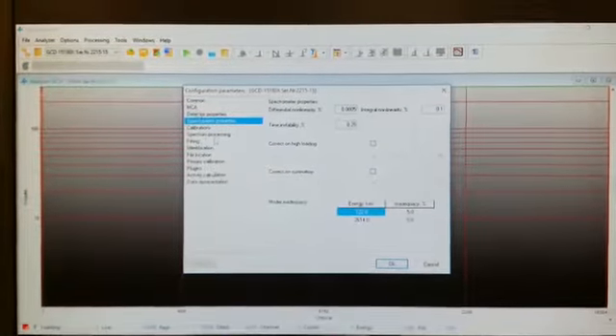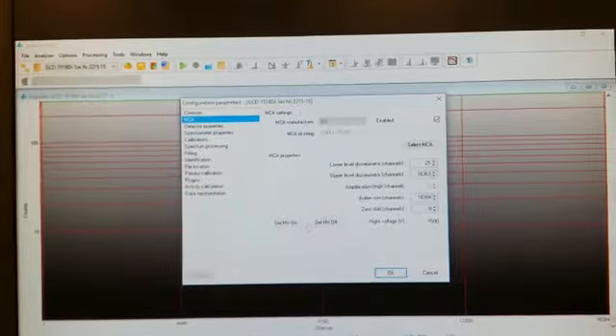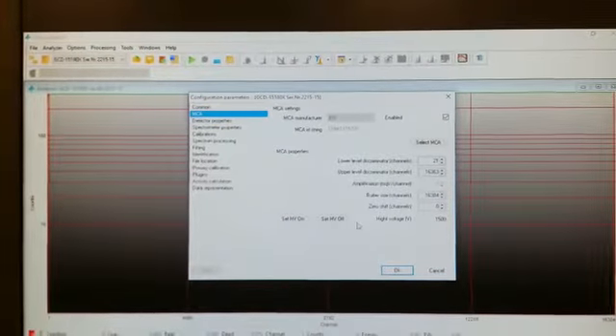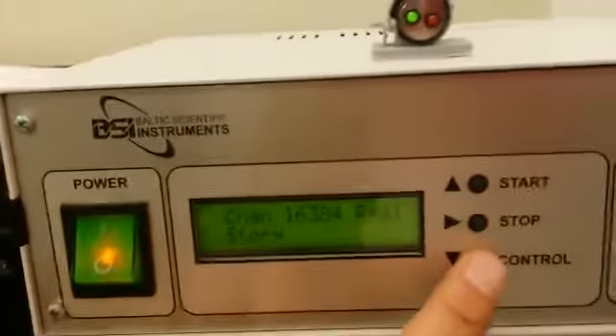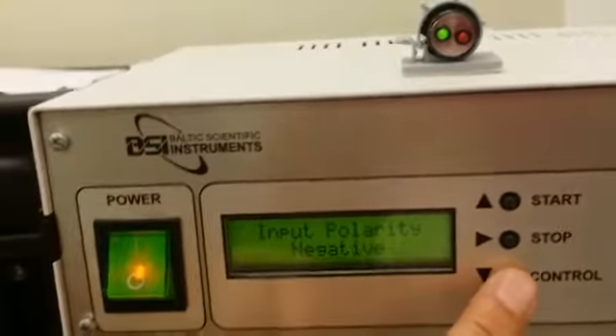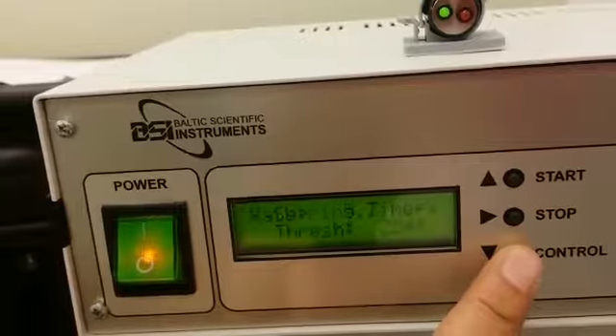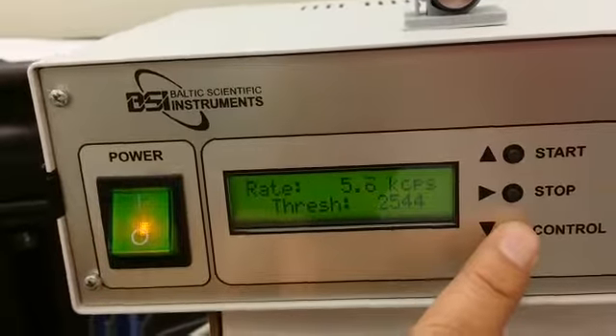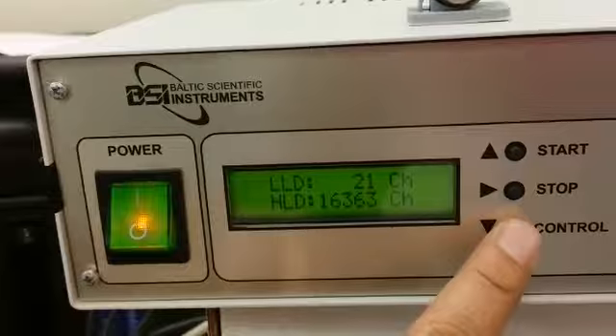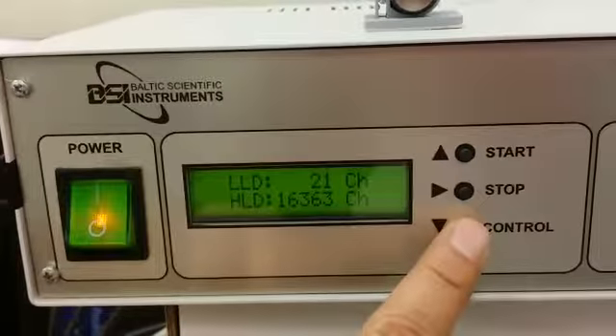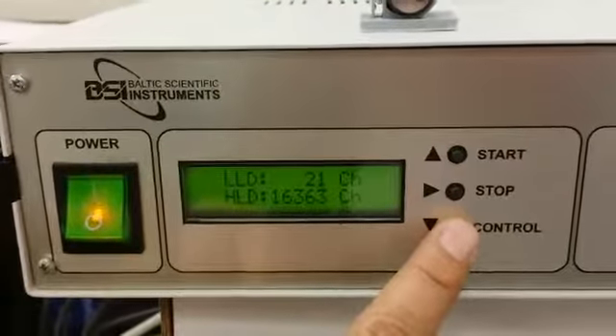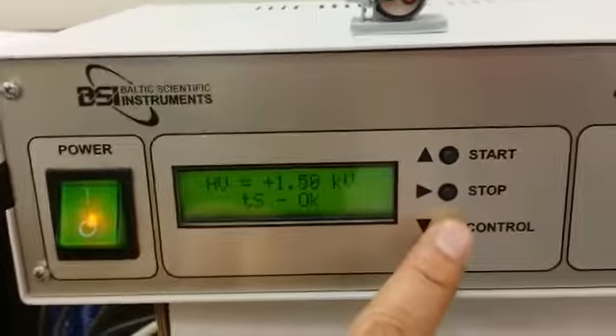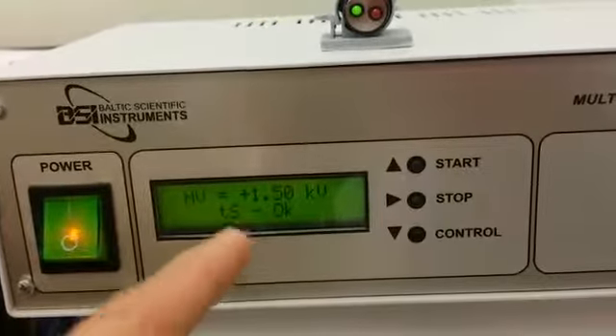I think you don't have to change anything here, except you can see that yesterday we went through the controls. Now you need to shift your camera here, and by looking at the controls, we went through input polarity negative, shaping time T2, rate, just ignore whatever the rate is in there, the lower level discriminator of channel 21, higher level discriminator of channel 16363, and we set our high voltage for our detector at 1.5 kV positive, temperature sensor showing as OK.